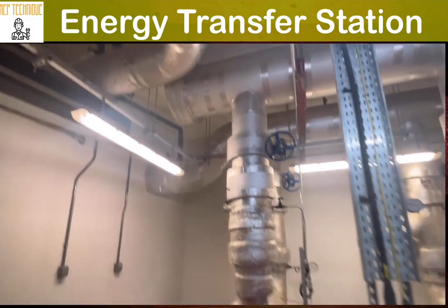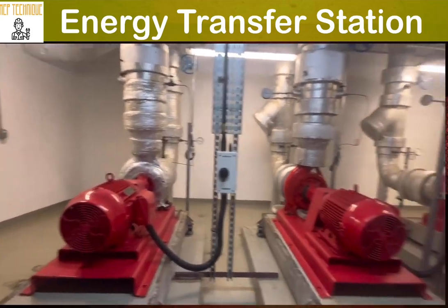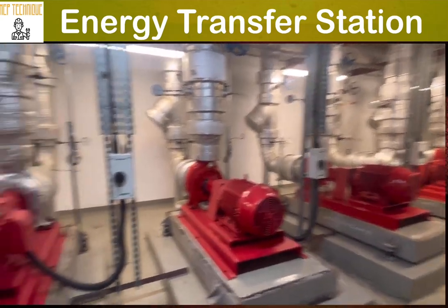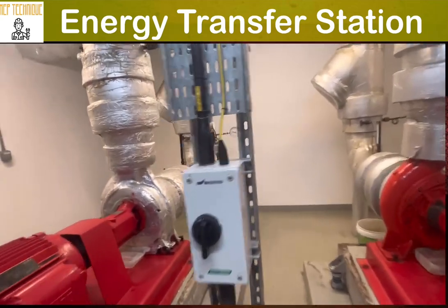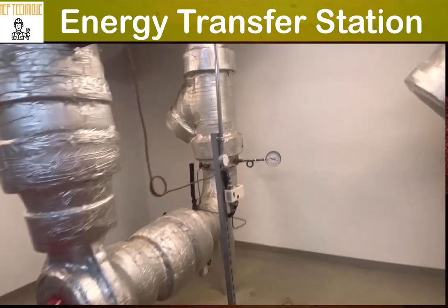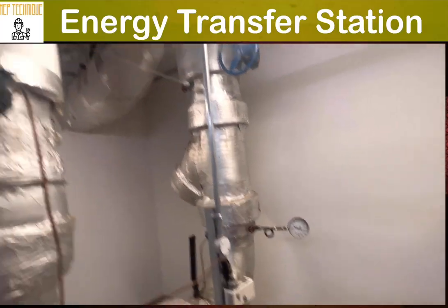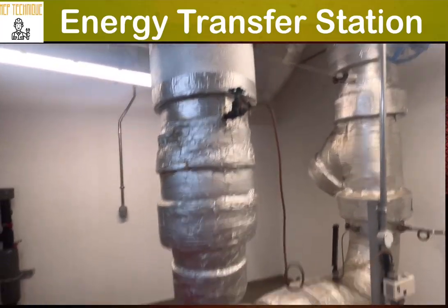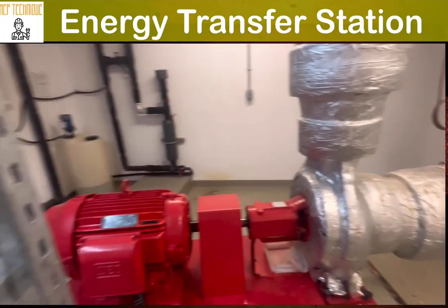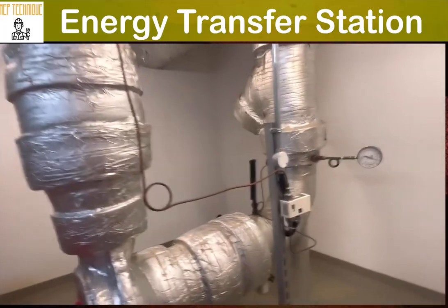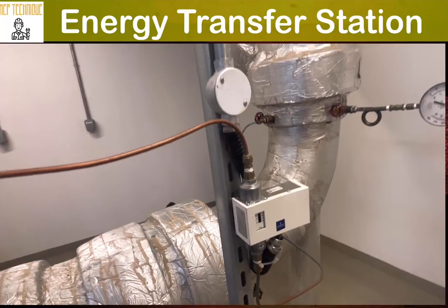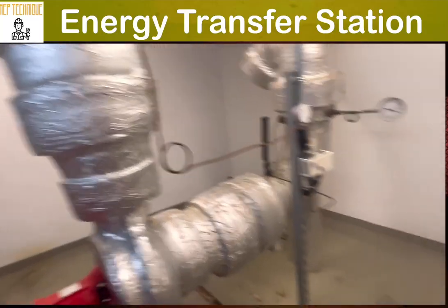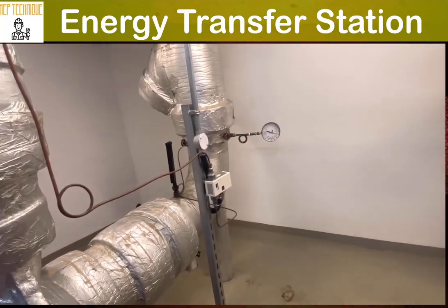Then you can see there are lots of pumps connected to our chilled water line. In the pump, you can see there is suction and discharge. In the suction there is a pressure gauge, and at the discharge also there is a pressure gauge to monitor the pressure. And across the pump, you can see there is a differential pressure switch to monitor the pressure across the pump, which is integrated with our DDC panel.